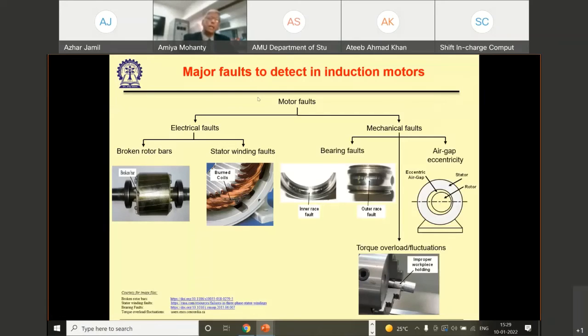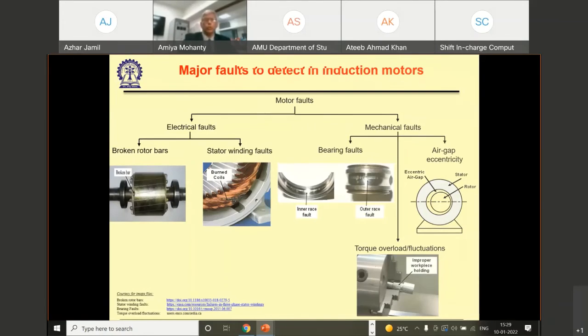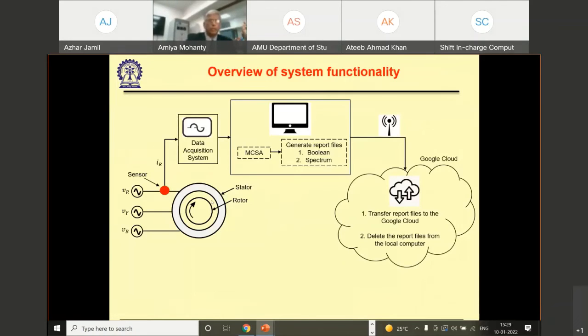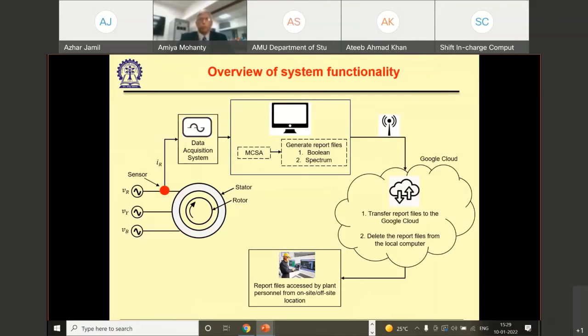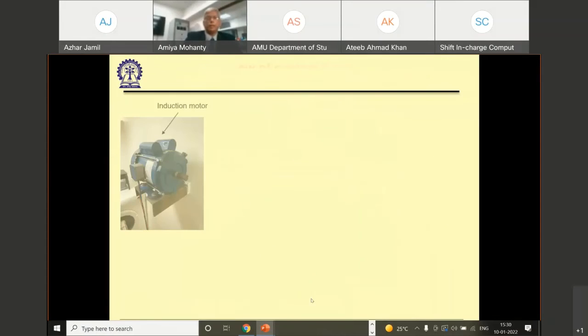All these faults get manifested in the motor current being drawn by the motor. So here's what we have done: we have a motor, we measure the current, we have a data acquisition system that transports data to a mini computer which does the analysis, generates report files, tells in Boolean terms what kind of fault is there and the spectrum of that fault, and sends it to the cloud. The report is in the cloud, anybody can access it. This is a technology we developed at IIT Kharagpur, and the report can be accessed by on-site or off-site personnel at different locations.